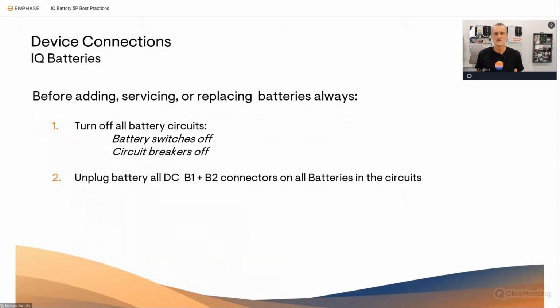When servicing or adding batteries to a site, or replacing batteries, you'll turn off all the battery circuits — battery circuit switches off, circuit breakers off — and then unplug the B1 and B2 connectors if the battery needs to be moved on site. This means it's fully depowered before shifting it.